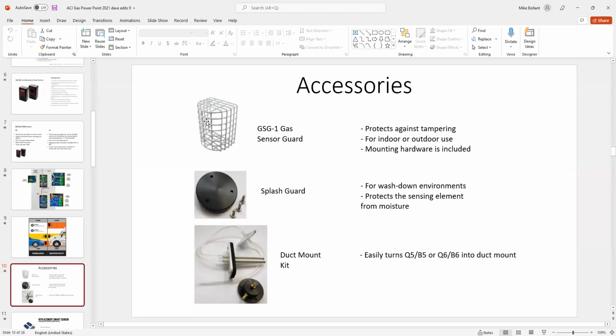Some accessories: we have the sensor guard. If you have a parking garage and you need to protect the sensor, depending on how and where it's at, that's basically selected job by job. We also have a splash guard. The splash guard helps protect the sensor in some washdown environments. For example, if you're putting a CO sensor and an NO2 sensor in a firehouse or an ambulance, and they're cleaning, washing down the vehicles or the fire trucks, and the sensors are close, sometimes it's wise to put in a splash guard to help save the sensor, because they don't actually know what that product is on the wall, and they just hose it down. So that's a good idea for those two types of applications. And a duct mount kit, if you have to put it in a duct, we have that apparatus as well.